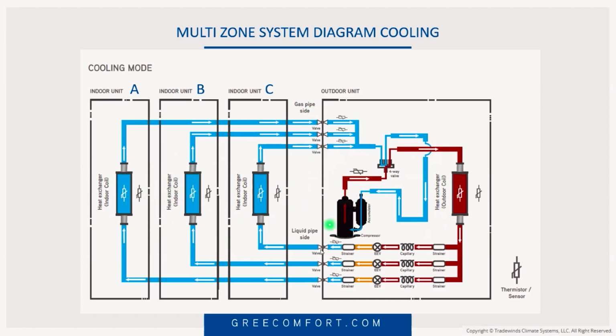You can also do it with the service tool, which we'll talk about. So, could you have one of these circuits not being right? Yes. There's another thing. You've got a liquid thermistor and a gas thermistor for each circuit. If one of these thermistors is out of range, it's also going to cause a flow problem into that coil. So you could have a fully charged system, this circuit works fine, C works fine, B works fine, A works terrible. And it could simply be that you have one or more of those thermistors out of range.